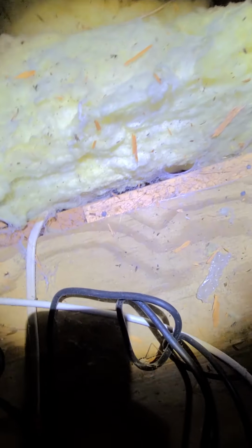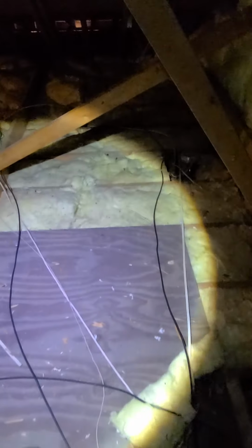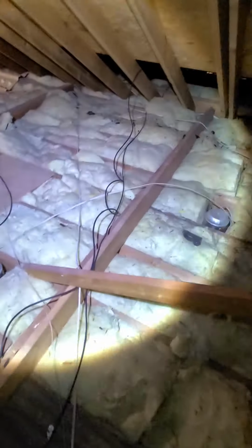Continue back over here. All this insulation is in pretty good shape. Great thing about insulation values is they stack. Here we've got some more air leakage because we've got spider webs, and where they live we have lots of fresh air moving in between the conditioned and unconditioned space. So again, this is a good candidate for air sealing and insulating, and bringing the R values here up to R60.